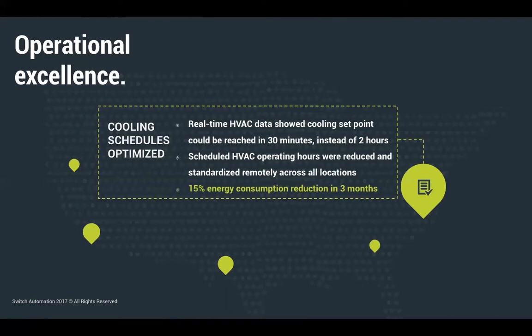Remember that cooling schedule I mentioned before? The platform they integrated was able to remotely connect their HVAC systems with their utility bill management system and occupancy counters, then layer analytics over the data from all those sources. As a result, they identified that to reach a comfortable space temperature before stores opened, they only needed to start running air conditioning 30 minutes before opening—much less than the 2 hours they previously thought.